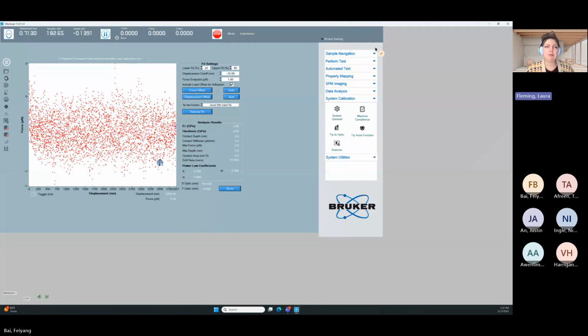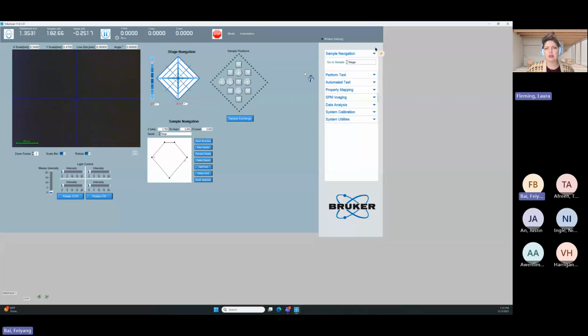Okay, so we're going to start by defining our sample zones. There are 3 different ways to define samples. On the system, we're going to start with the most basic one, which is we need to focus on the sample surface. So we've been brought back to the sample navigation screen, which is great. On this screen, we can see we have an optical view that right now is dark because our X, Y, and Z are in the home position, meaning we're not over anything, we're just homed.